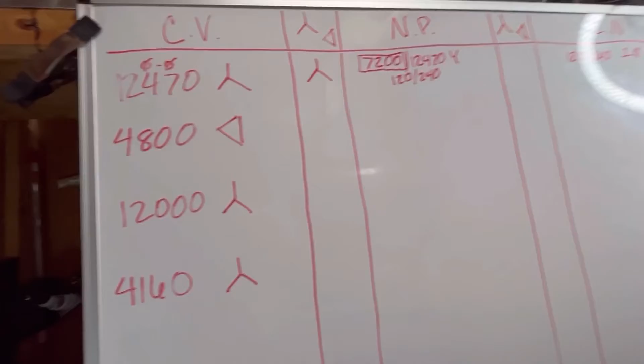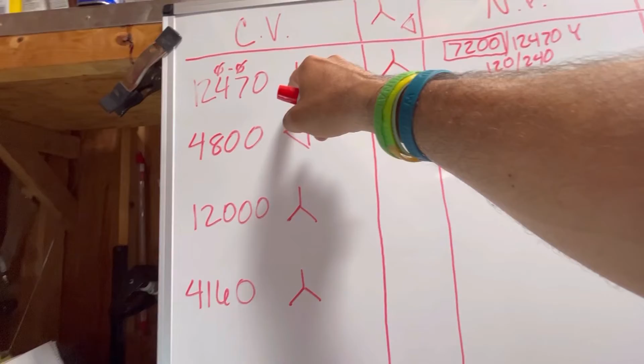So an even quicker, easier little hack is this. Check this out. If this number is the same as this number, it will be a delta. I'll say it again. If this number is the same as this number, the hookup will be a delta. If it is not, which is what we have here, it's going to be a Y. All right, so moving on, the next thing we have to look at is our customer needs. Customer needs determine my hookup on my secondary side, not the nameplate.